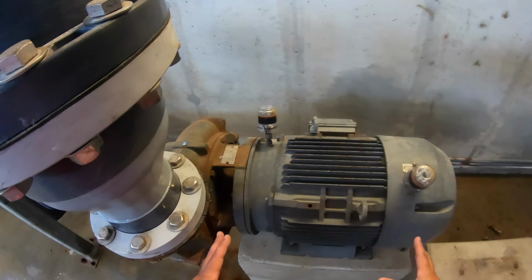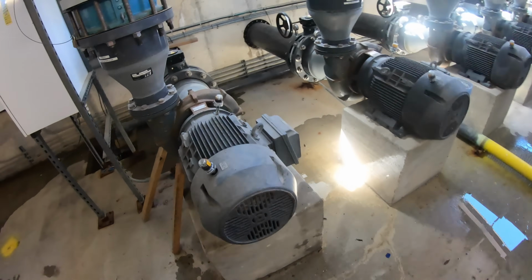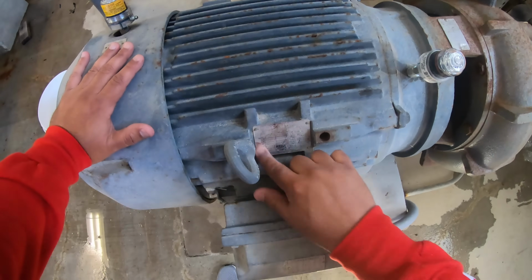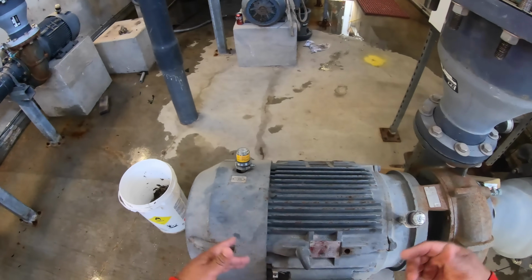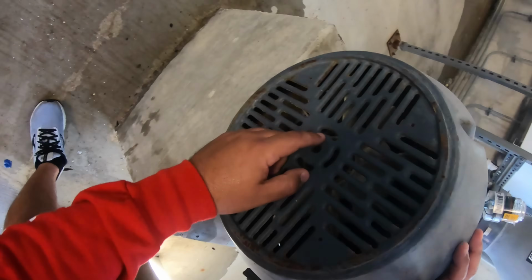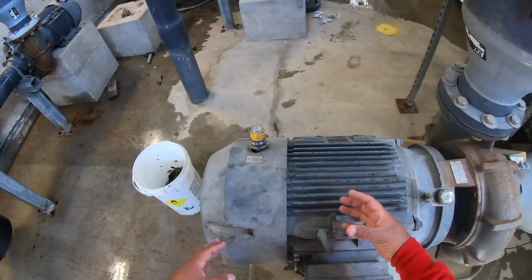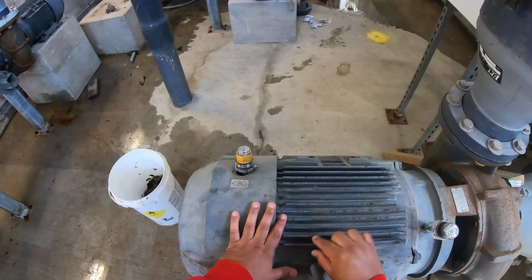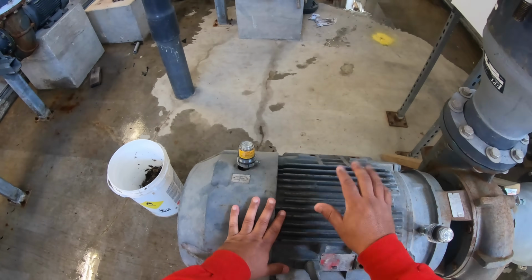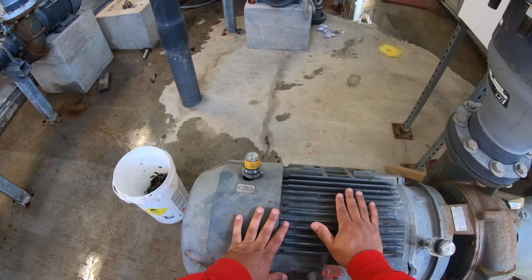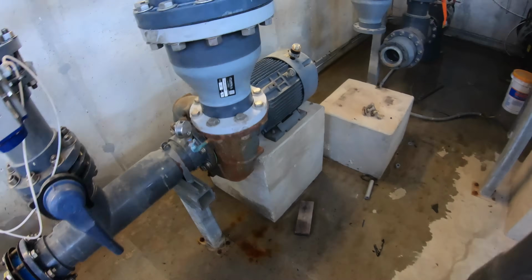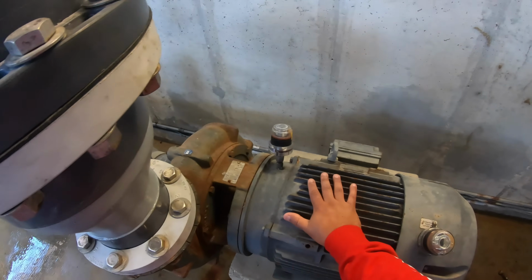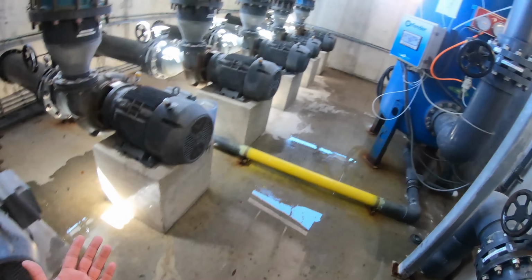And these motors are called TEFC. So I'm gonna look at this one. If we look, it's gonna be hard to see it, but this is a TEFC, which stands for totally enclosed fan cooled. So there's a fan right here, and that fan takes air from back here and blows it onto these fins, which is like a heat sink, okay? So that's all that is, okay? And it feels really good. So having the fan on your motor is very important because it's fan cooled.